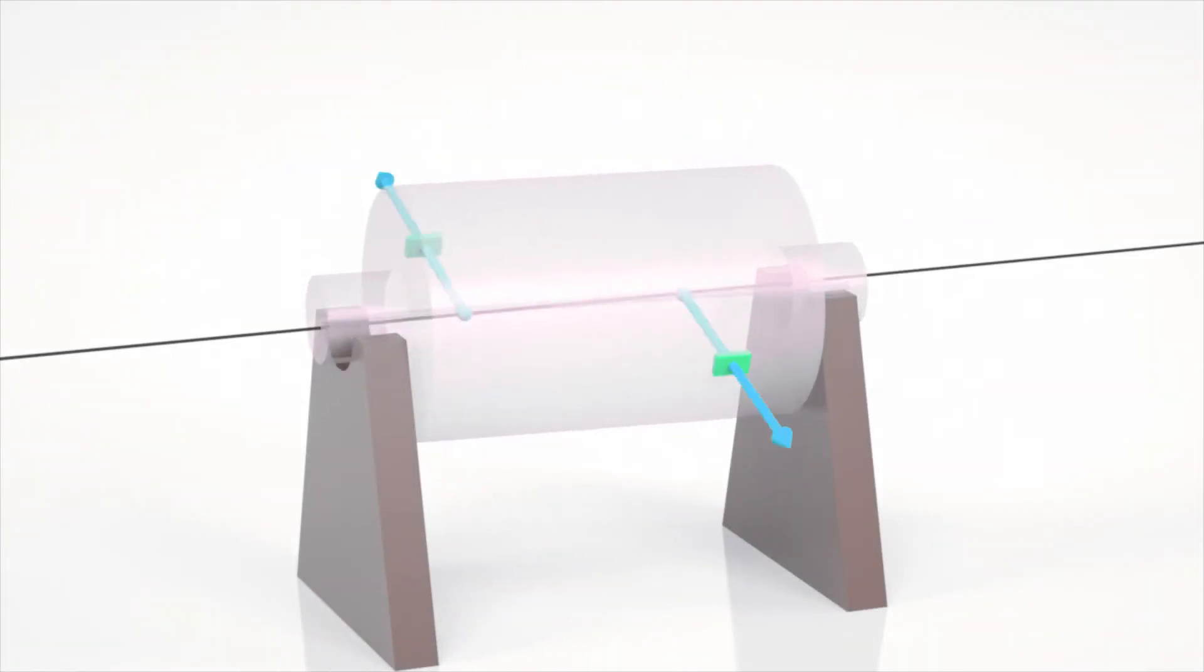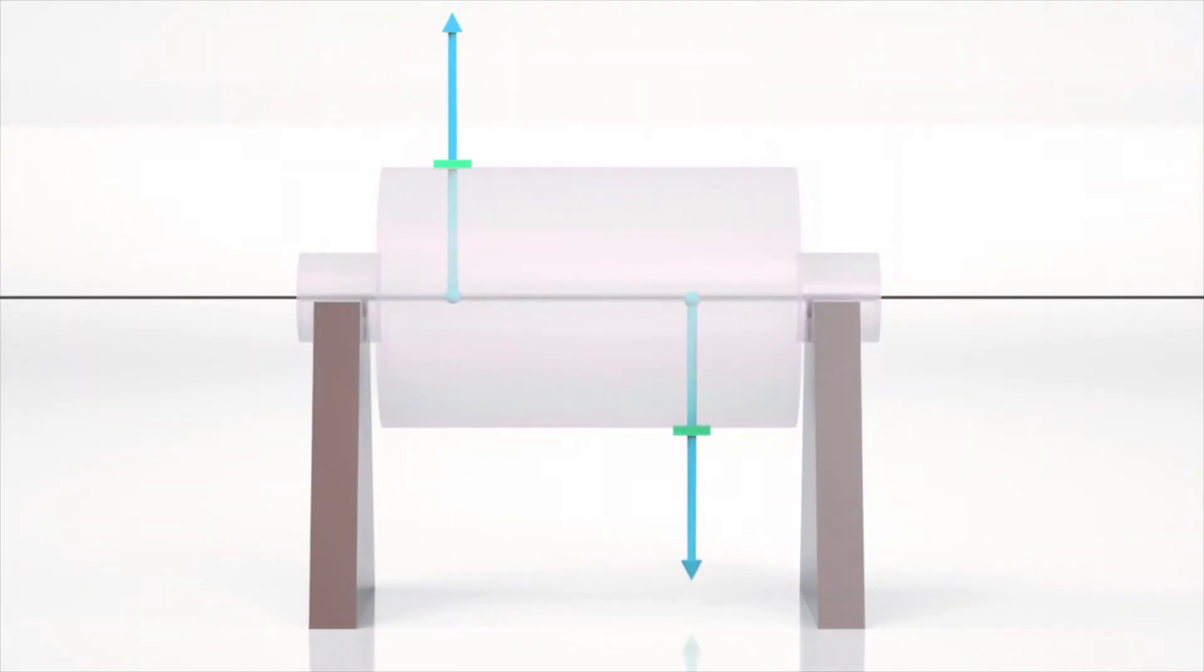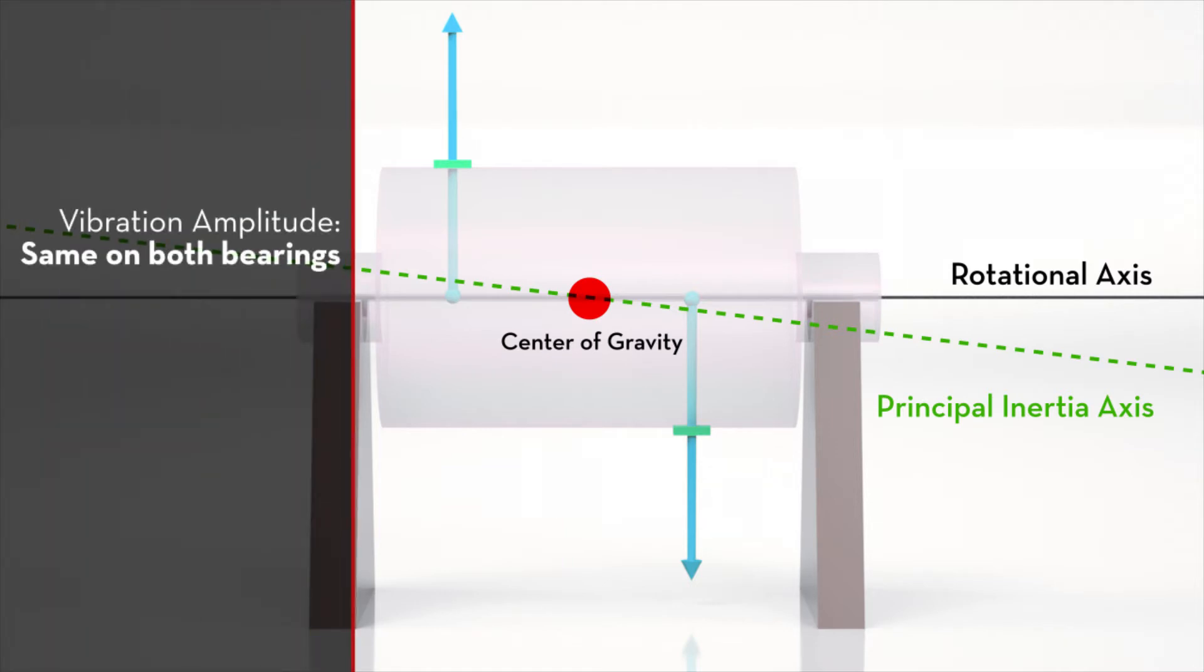Couple unbalance occurs when the principal inertia axis is displaced from the rotational axis and the axes intersect at the center of gravity. The two axes are not parallel. The rotor is statically balanced. The vibration amplitude will be the same on both bearings. The phase angles will be 180 degrees different.